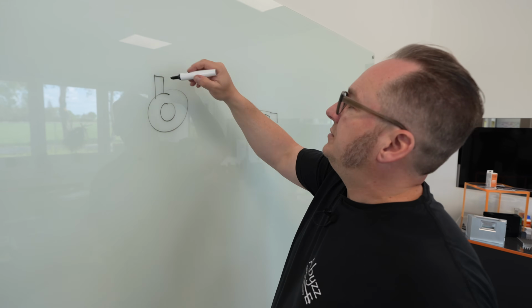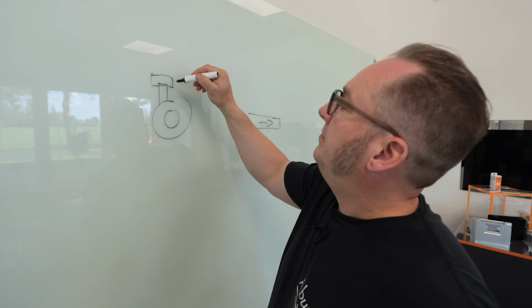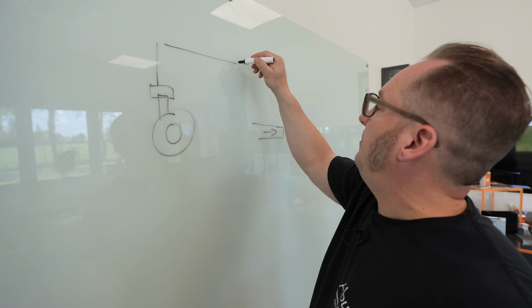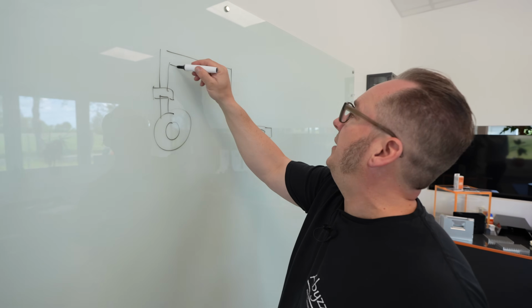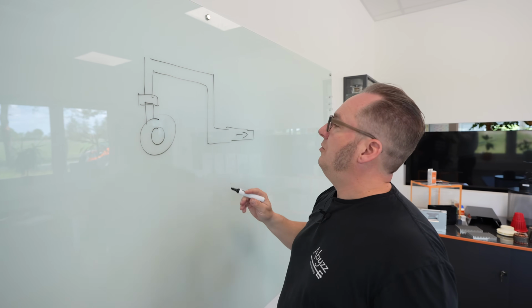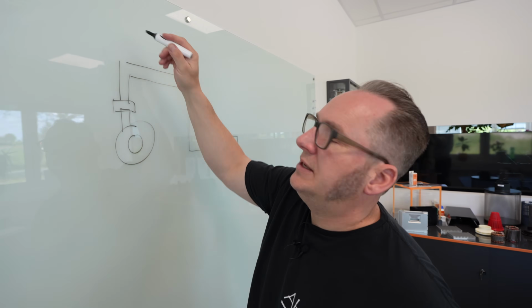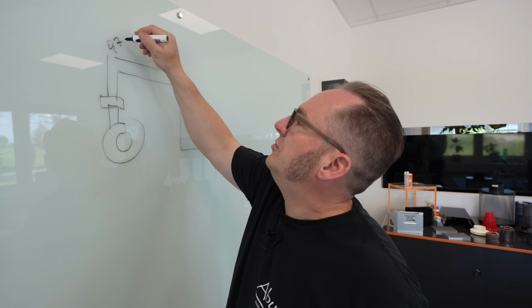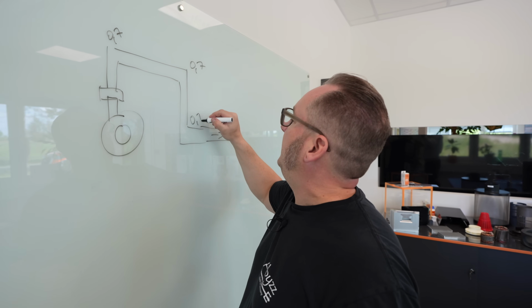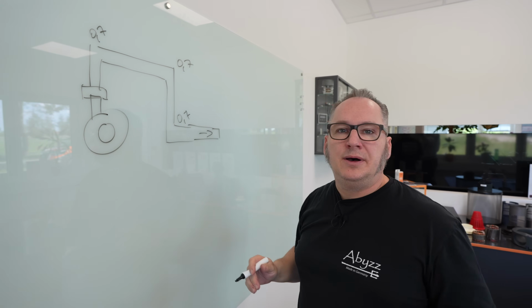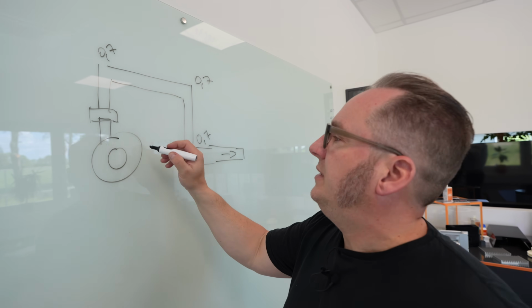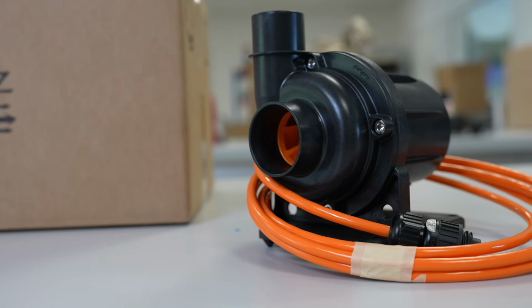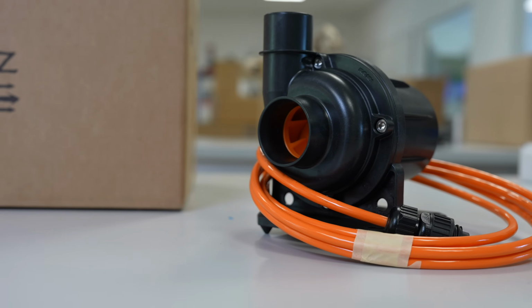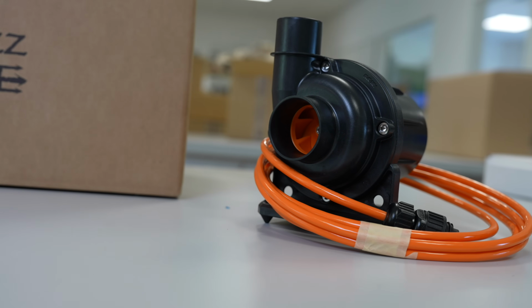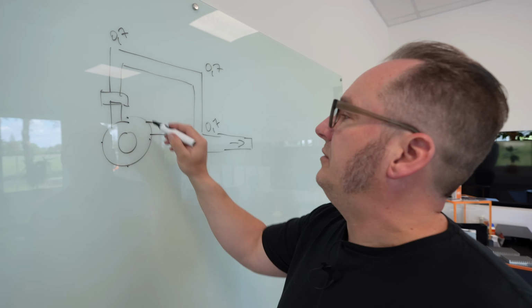So what they did was they made their bulkhead fitting, and then they went up, and then they went down, and then they went into the pipe. So, which gives you 90s, and it's 0.9 or 0.7, but you can look that up in any handbook just to have a number. What they should have done is just unscrew those 4 screws we offer on the A200 and A400, and then you can actually turn the pump head around to point into this direction.